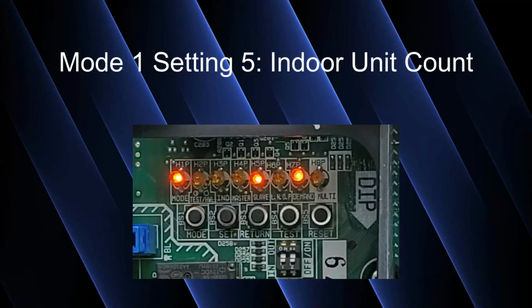Anyways, when you press the set button 5 times, you should have a binary value of 5 shown on all of these LEDs, which is H5P and H7P. 4 plus 1 equals 5. H1P will continue to flash. That is indicating that you are in the monitor mode menu, and that's fine. You can go ahead and ignore H1P for right now, but I'll continue to bring it up just to try to keep you guys on the right track.